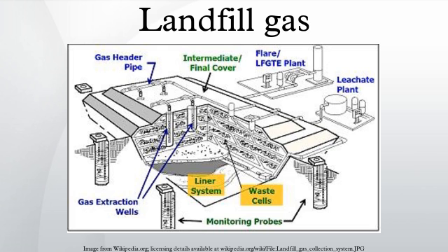Landfill owners and operators must make sure the concentration of methane gas does not exceed 25% of the LEL for methane in the facility's structures and the LEL for methane at the facility boundary. Landfill gas migration. Landfill gas migration due to pressure differentials and diffusion can occur. This can create an explosion hazard if the gas reaches sufficiently high concentrations in adjacent buildings.